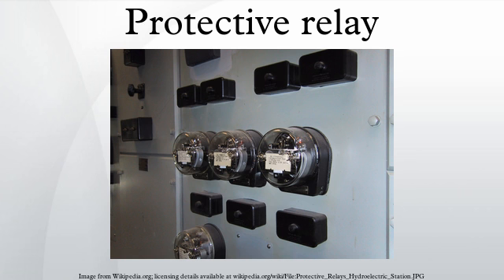It is also called the impedance relay as it calculates the line fault with the use of the impedance per meter of the transmission line. There are many types of distance relays including impedance distance, reactance distance, offset distance and mho distance. Current differential protection. Another common form of protection for apparatus such as transformers, generators, buses and power lines is current differential. This type of protection works on the basic theory of Kirchhoff's current law, which states that the sum of the currents entering and exiting a node will equal zero.